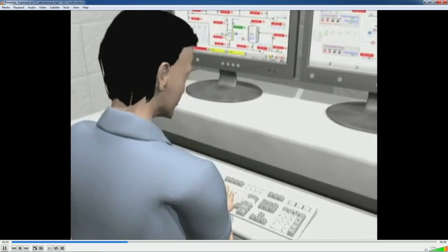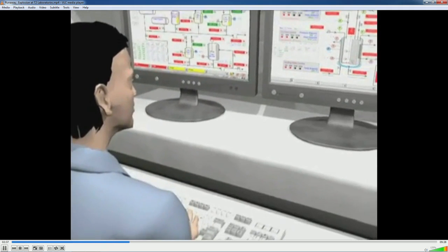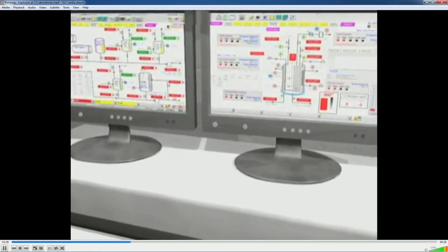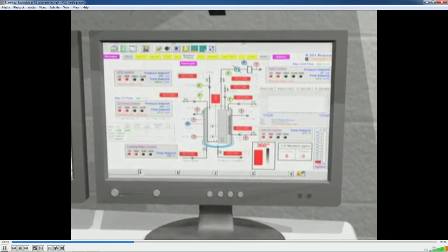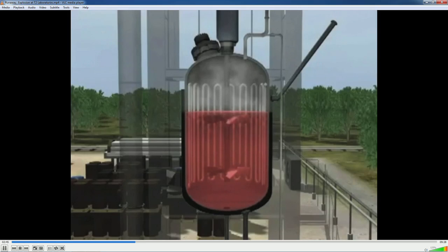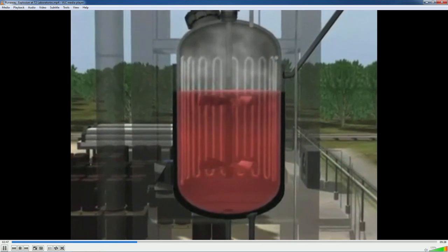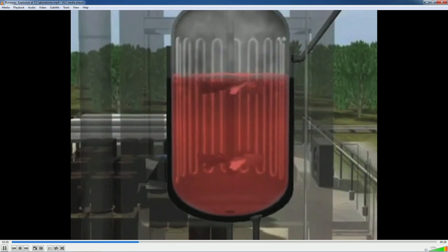However, on the day of the accident, the CSB found that the operator tried to cool the reactor as usual, but the cooling system likely malfunctioned, perhaps due to a blockage in the water supply piping or a valve failure. The temperature and pressure inside the reactor began to rise uncontrollably in a runaway chemical reaction.